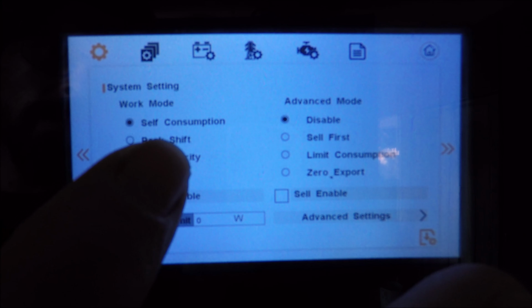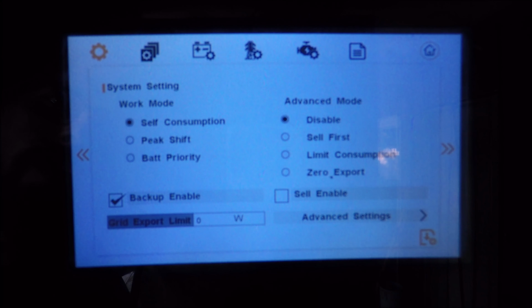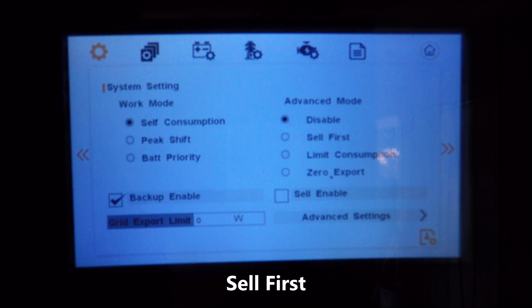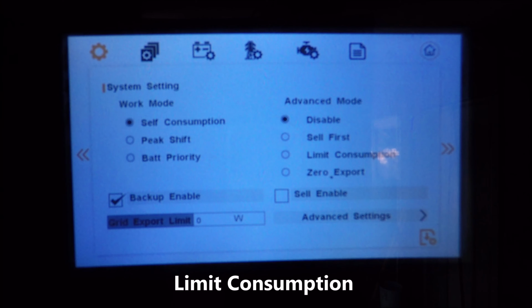If you choose any of these advanced modes, the inverter ignores any settings for work mode. Advanced mode overrides work mode. We're going to go over limit consumption, sell first, and zero export. Sell first prioritizes selling power to the grid. You have to enable it, and once you do that, you can use additional settings like time of use, grid charge, PV first, battery first, and you can use CT power limits to set the power limits from the current transformers. Limit consumption feeds power to the grid, charges the battery during specific times.